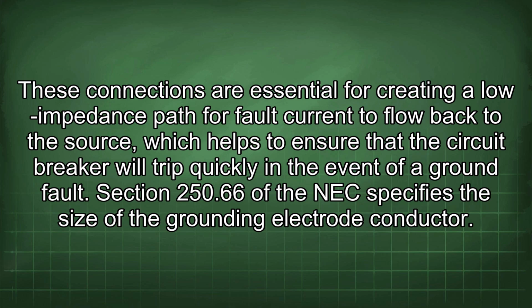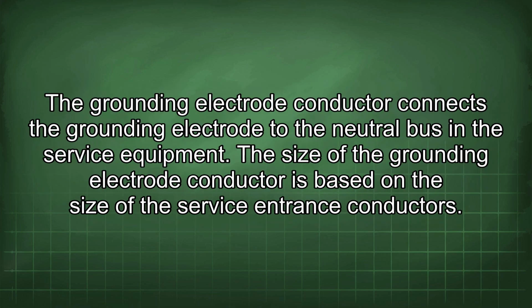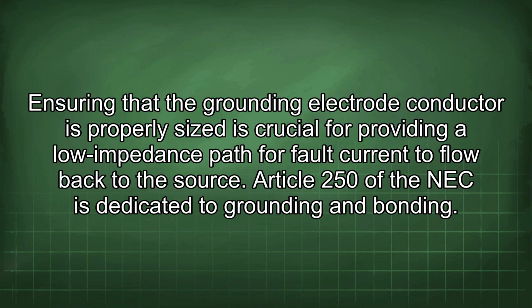Section 250.66 of the NEC specifies the size of the grounding electrode conductor. The grounding electrode conductor connects the grounding electrode to the neutral bus in the service equipment. The size of the grounding electrode conductor is based on the size of the service entrance conductors. Ensuring that the grounding electrode conductor is properly sized is crucial for providing a low impedance path for fault current to flow back to the source.